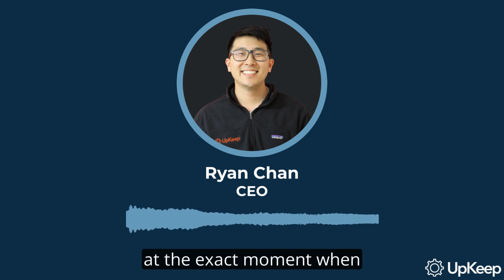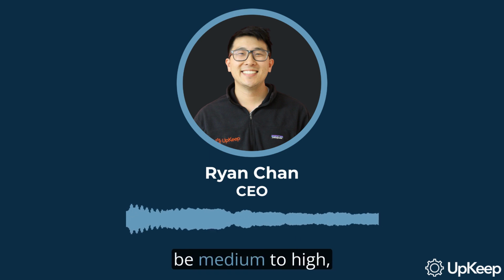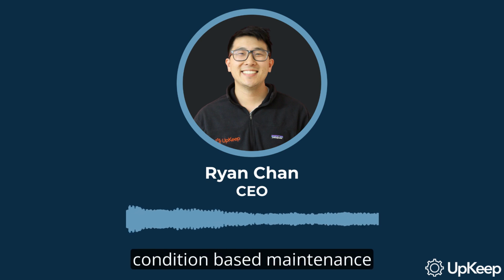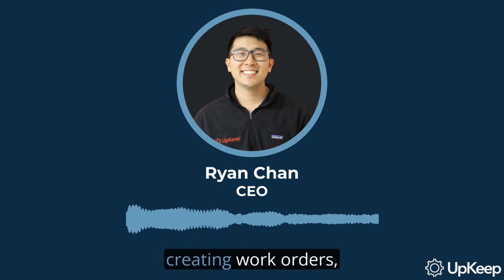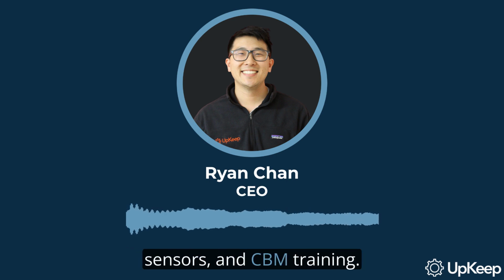Now let's talk about condition-based maintenance. This is work that is performed at the exact moment when measured parameters reach unacceptable levels. The trigger for the workflow is the measured parameter level. The startup cost can be medium to high, and the cost savings are dependent on the amount of equipment using CBM. The resources you'll need for condition-based maintenance include maintenance software for dispatching technicians and creating work orders, condition monitoring software, condition monitoring tools and sensors, and CBM training.